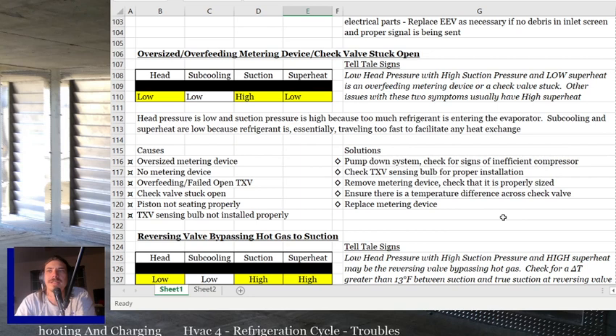The way to know that this is an overfeeding issue and not something else is that the superheat is low. If you've got low head with high suction but a low superheat, then you've got too much refrigerant moving through the metering device somehow. You've got to figure it out. So again, telltale signs of an overfeeding metering device or a check valve stuck or something similar are low head pressure with high suction pressure and low superheat. Other issues with these two symptoms usually have a high superheat. Head pressure is low and suction pressure is high because too much refrigerant is entering the evaporator.